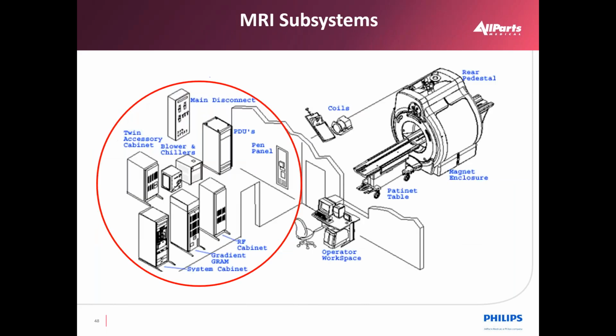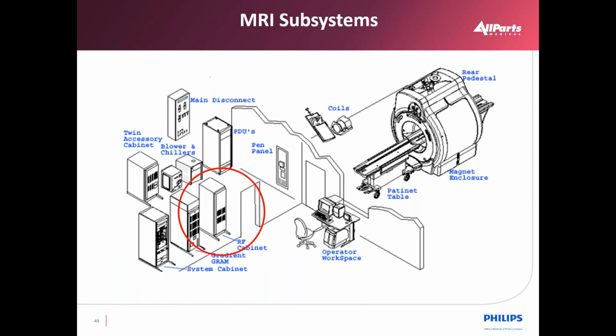The equipment room contains the system control section, which processes the data from the scan, the RF amplifier section that directs the RF signals, and the gradient amplifier section where the gradient field is adjusted. The components inside of the RF amplifier section produce the radio frequencies that excite the patient's hydrogen protons. They are also used to maintain communication between the RF subsystem and the system control section.